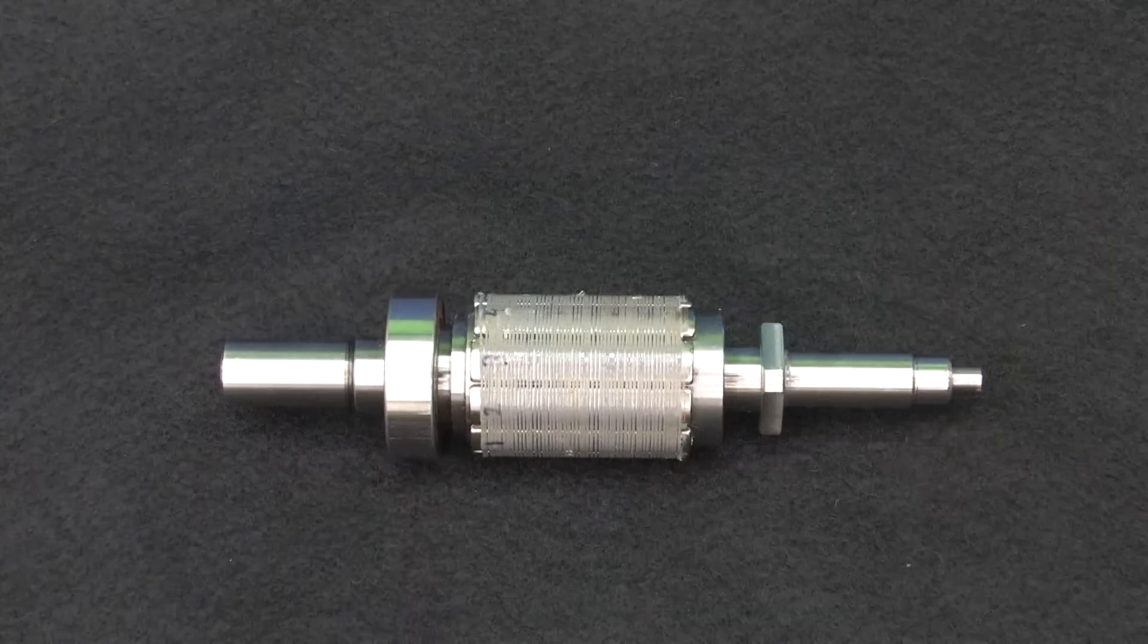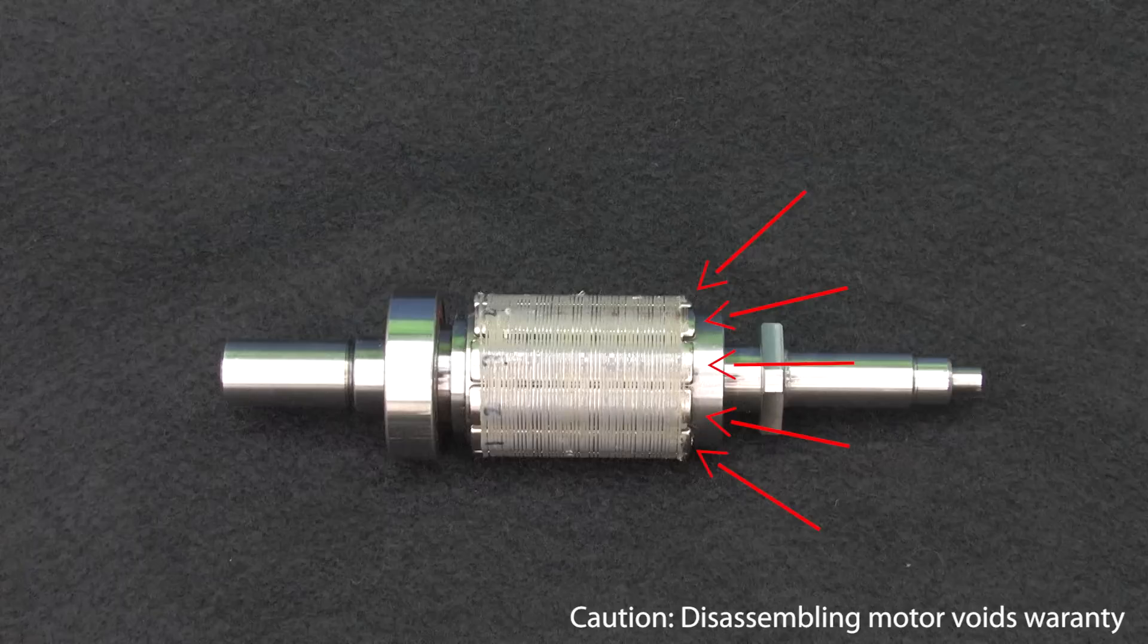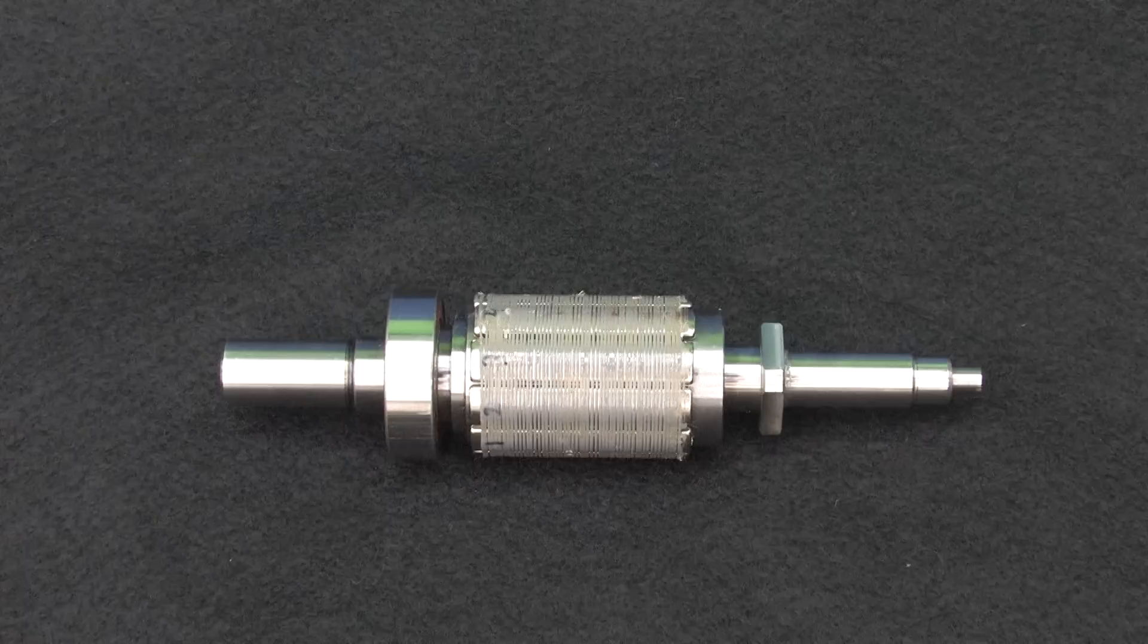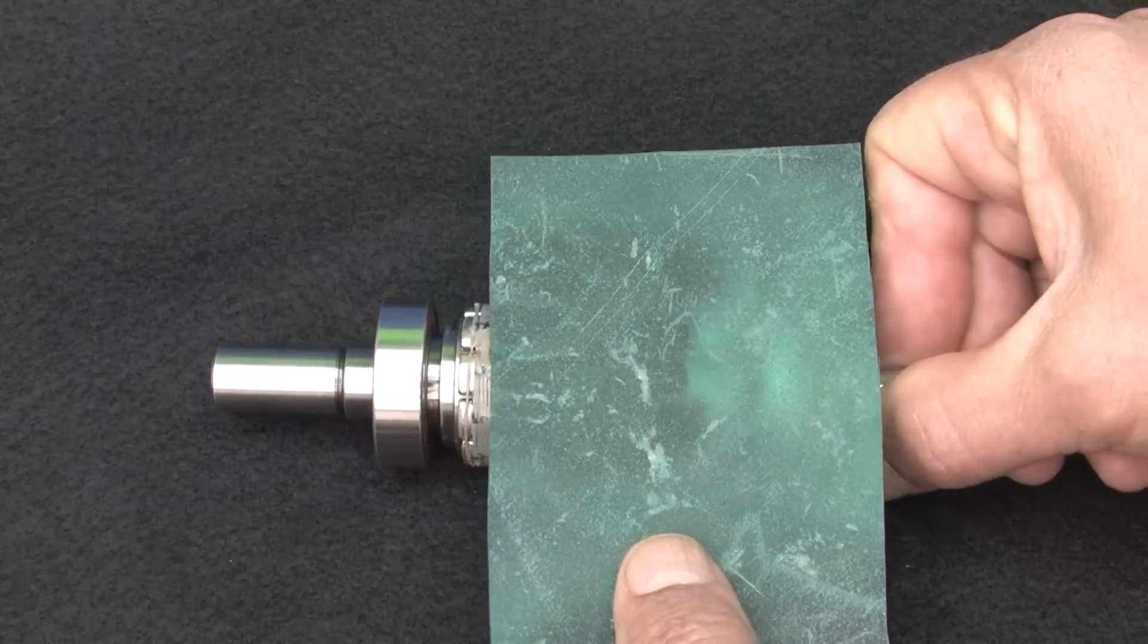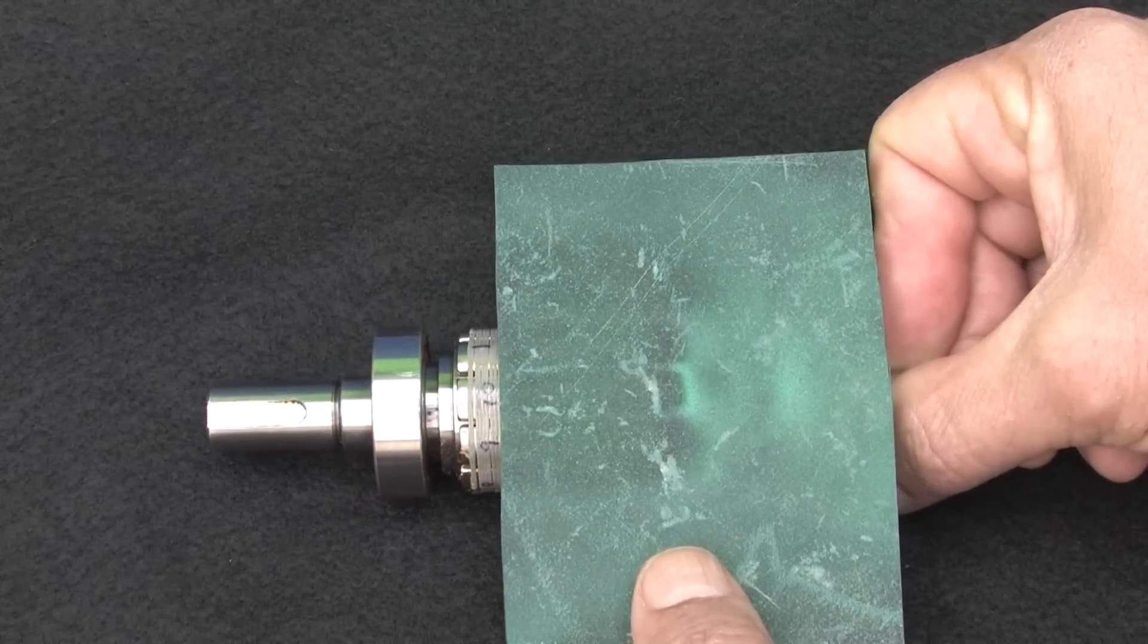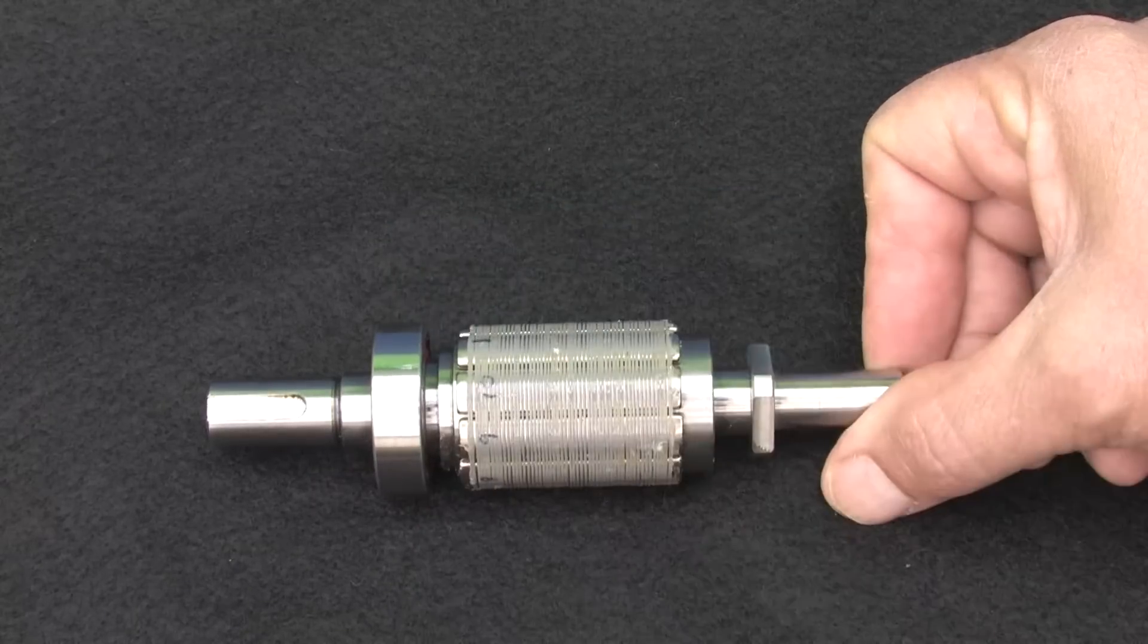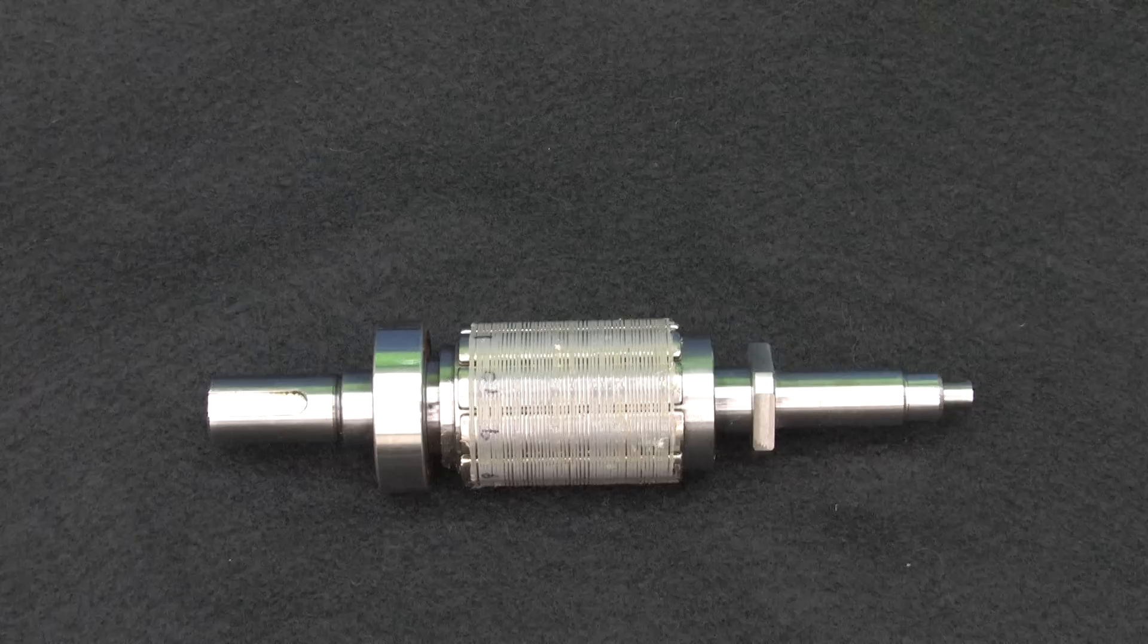Here is a disassembled SureServo 2 motor. On the rotor, we can actually see the permanent magnets attached to the shaft under this webbing. Using webbing instead of all that plastic helps keep the inertia low which makes the motor more responsive. And of course we can also see the magnets using the magnetic paper. And it looks like there's 10 of them on the shaft. More magnets equals smoother operation. Another reason the SureServo 2 system performs so well.